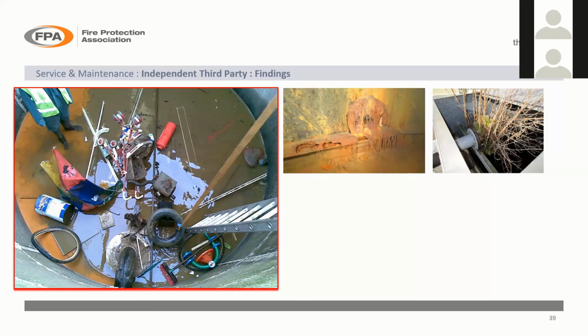Now, at the bottom of that picture, you can actually see the pump suction pipe. So that is where the water would be sucked into the pump in the event of a fire. Normally that tank would be full, and that pipe, when it comes to the wall, has got a vortex inhibitor on the bottom to ensure that water flows in nice and smoothly.